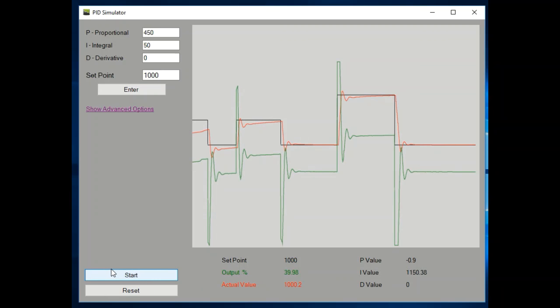Not a lot of people understand the derivative value. Its job is to take this overshoot and minimize it as much as it can. How the derivative does that — it looks at how fast the actual value is reaching the set point. The faster it reaches the set point, the more the derivative pulls back on the controller to stop that overshoot. Let's see how that works.